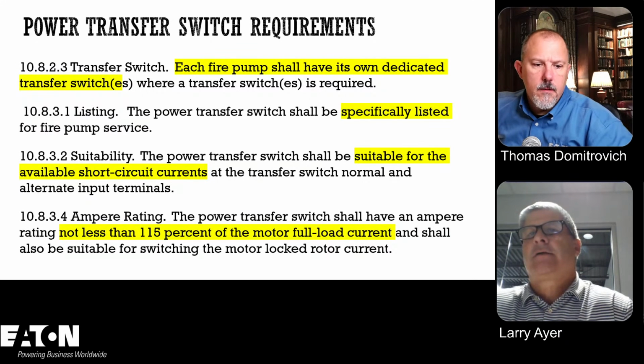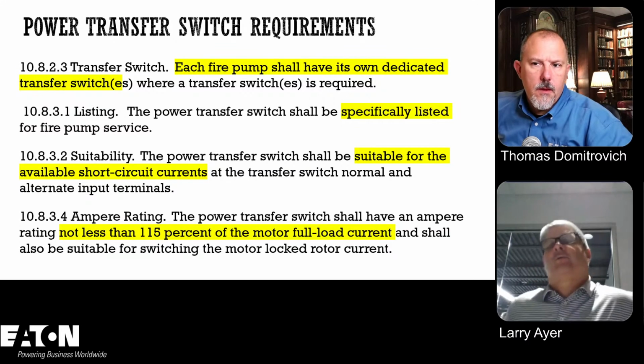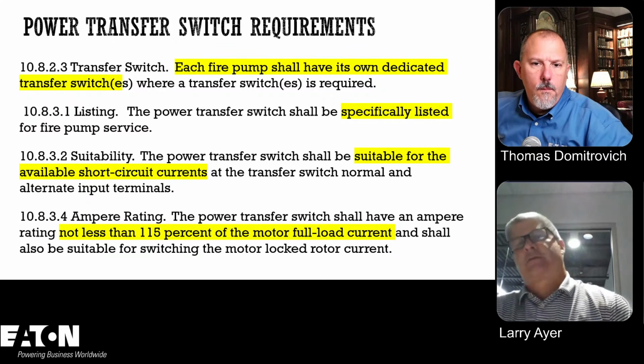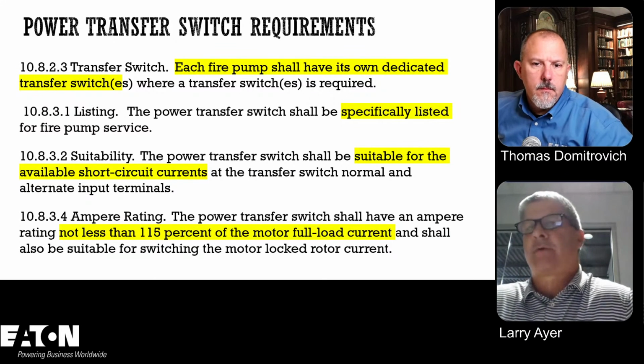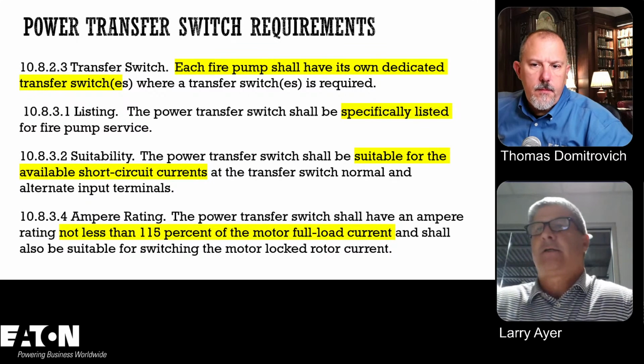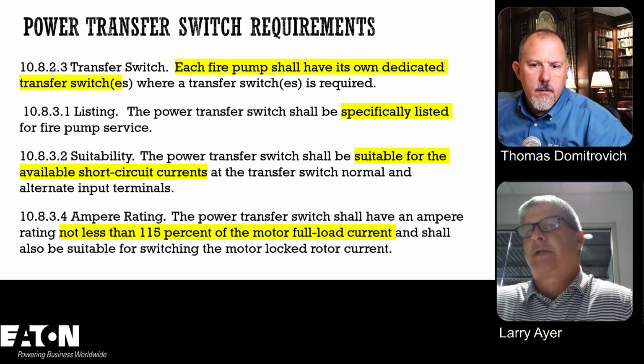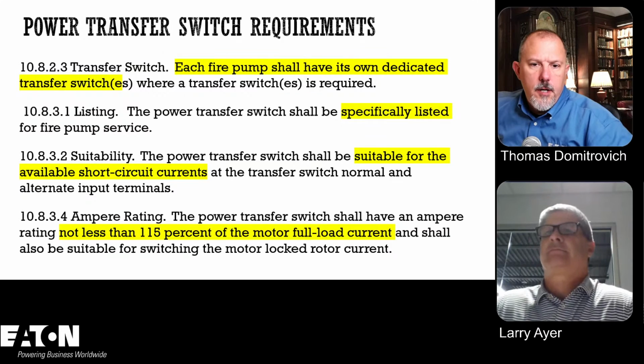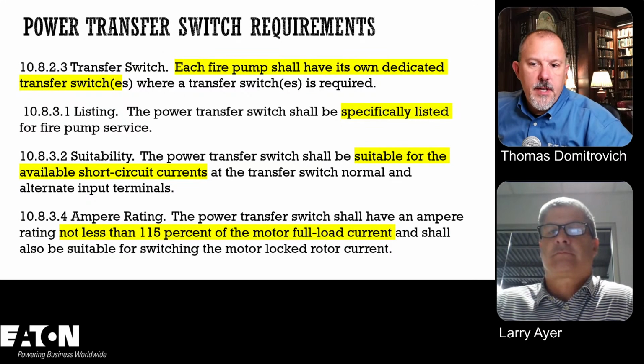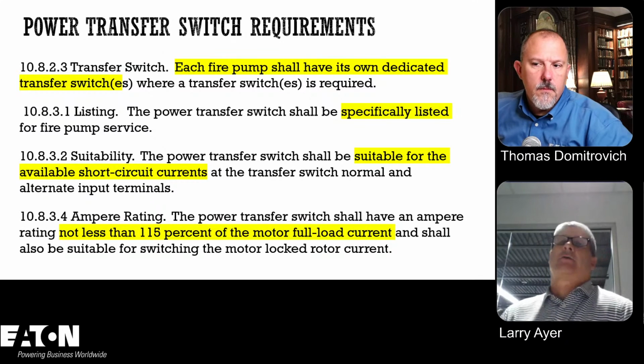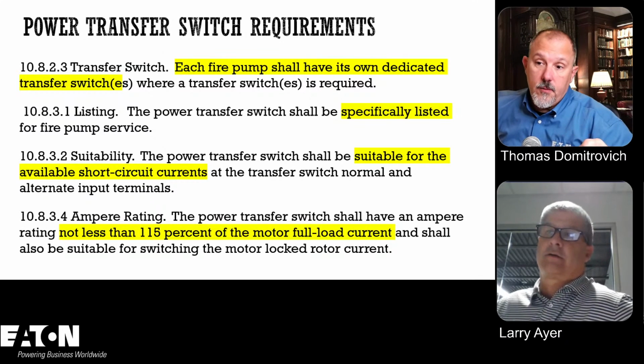Okay, so you could do that, but again, most people do not worry about it. A lot of people, sometimes I don't even see them put the Jockey pump on a generator. You can do that, but it typically comes off a branch circuit. So we said the ampere rating has to be not less than 115% of the motor full load amps. And Mather is saying, what about the locked rotor current? You do not have to size that for locked rotor current. You have to be able to switch the locked rotor current.